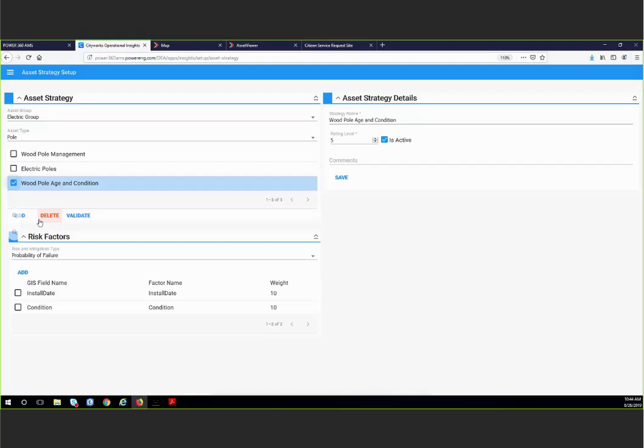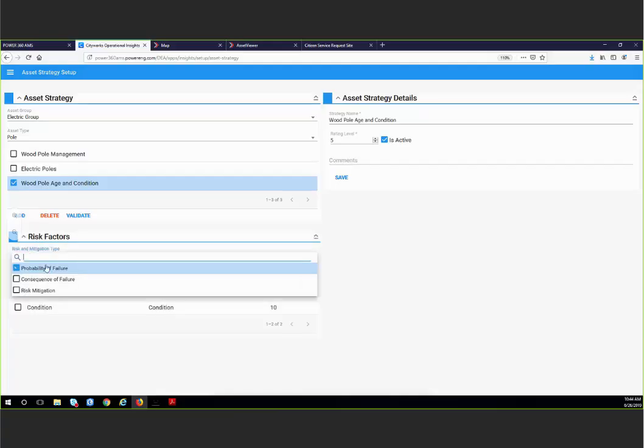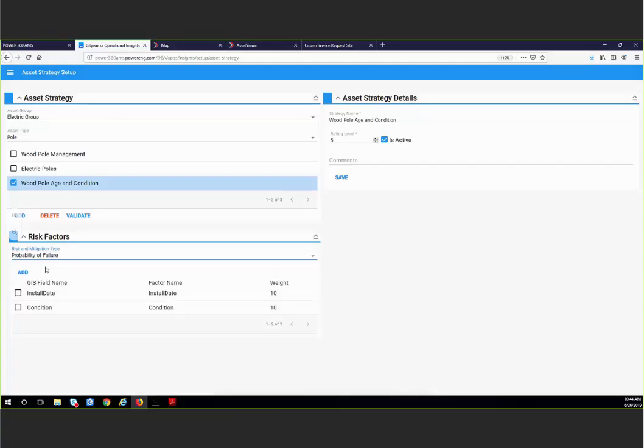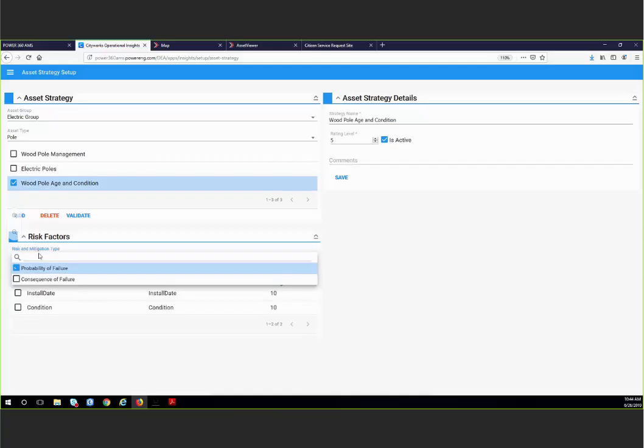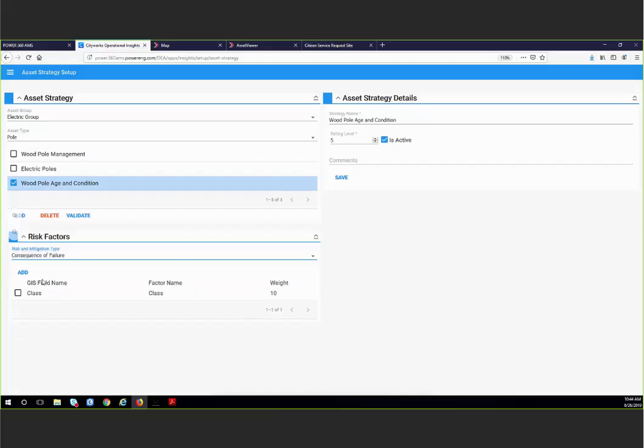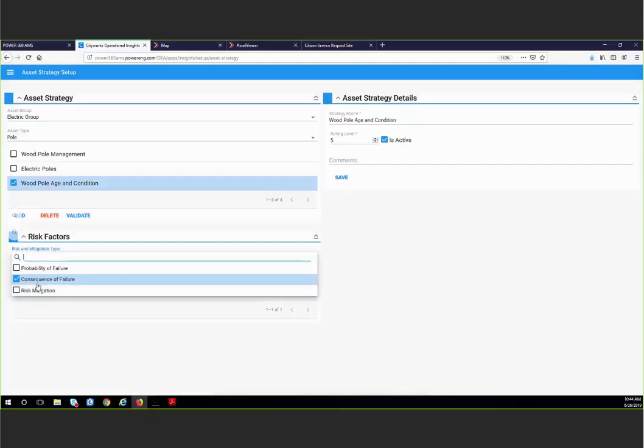Setting up this analysis requires, at a minimum, the calculation of the probability of failure. For this, I use the age and condition attributes of the pole. You need to specify the consequence of failure, and you can use other attributes of the asset for that. You could also optionally indicate factors for risk mitigation that will be taken into account in this analysis. Now I'll show you some previous analysis that I made using this strategy.